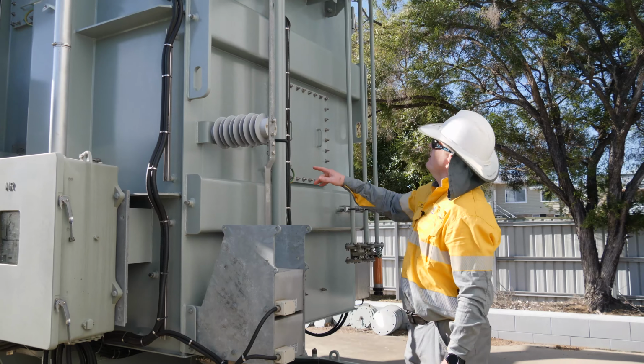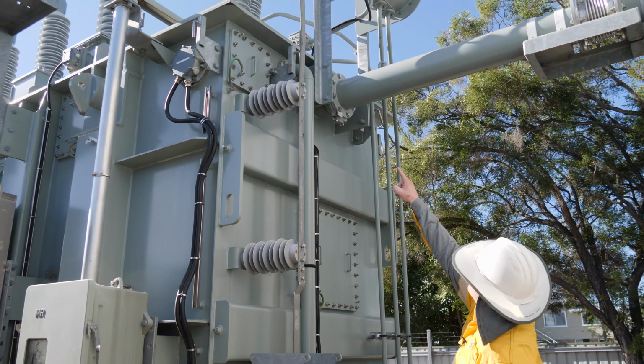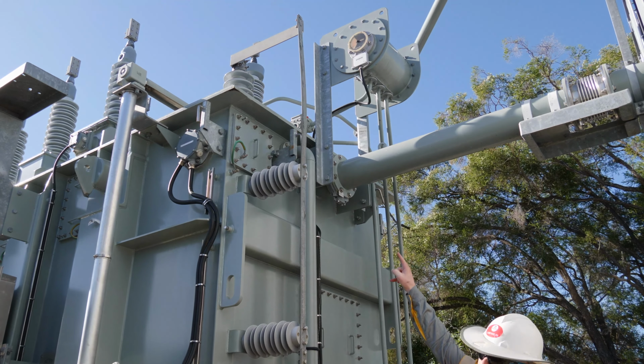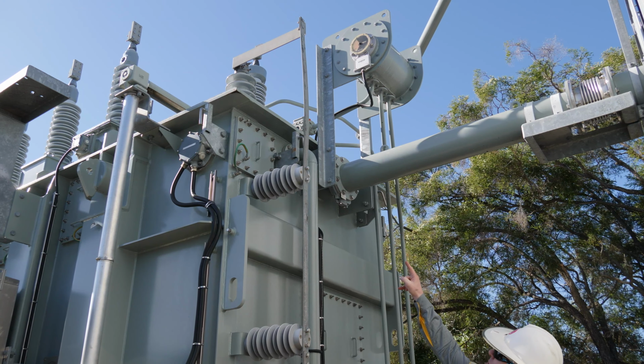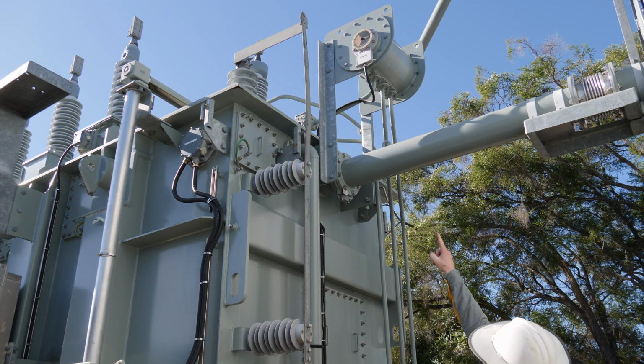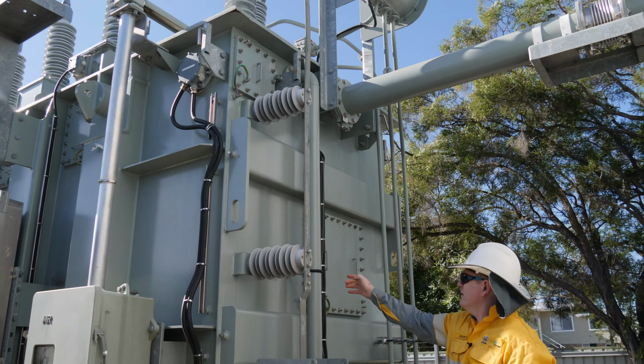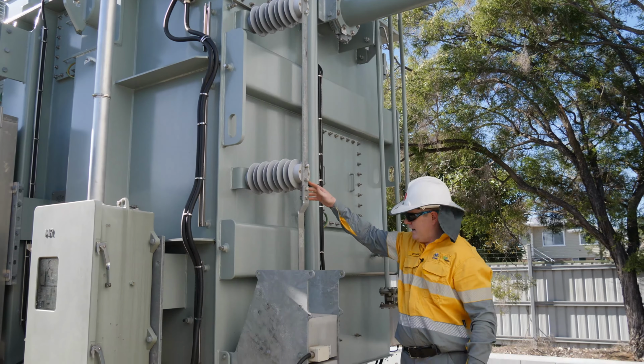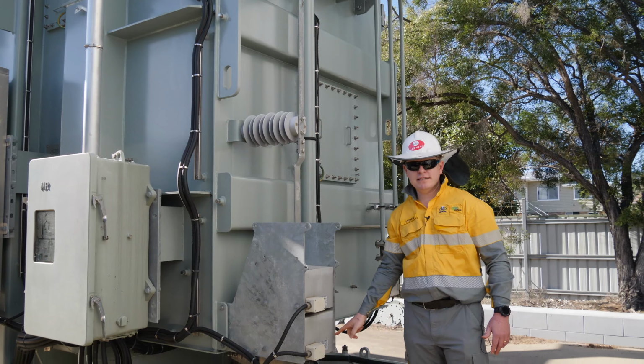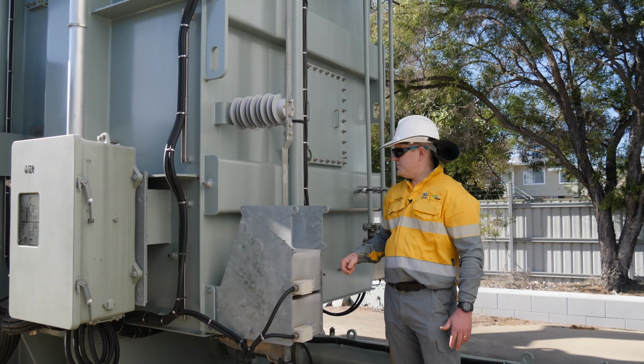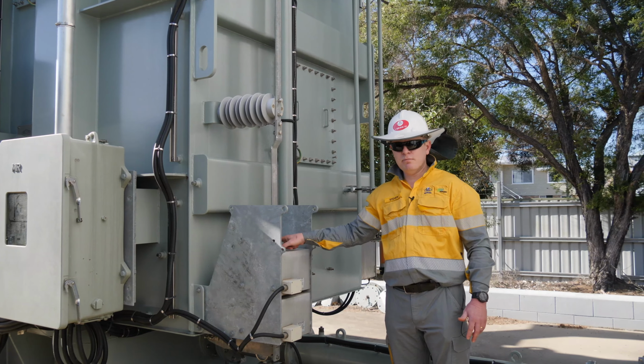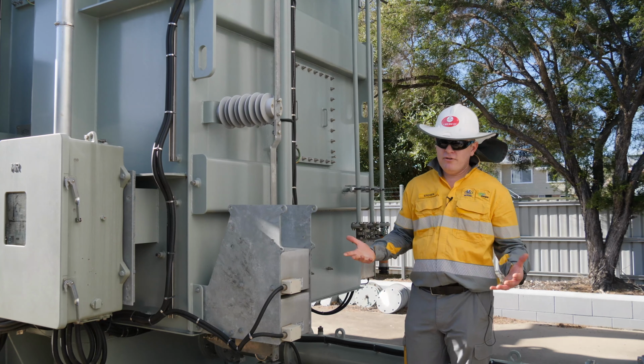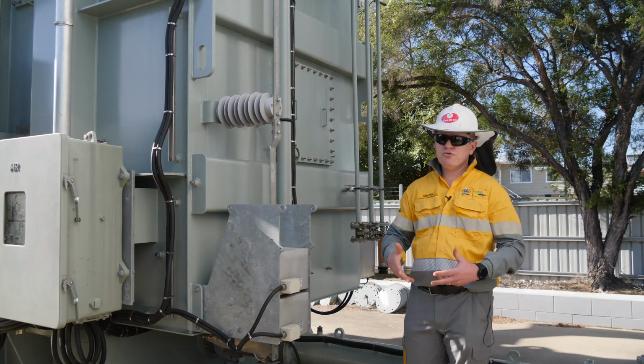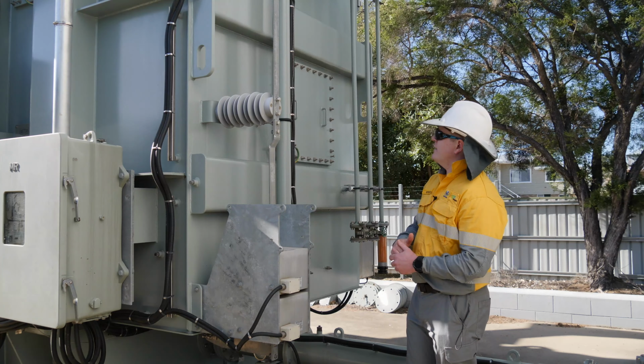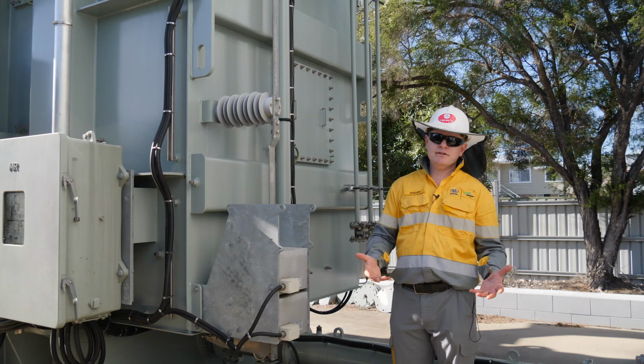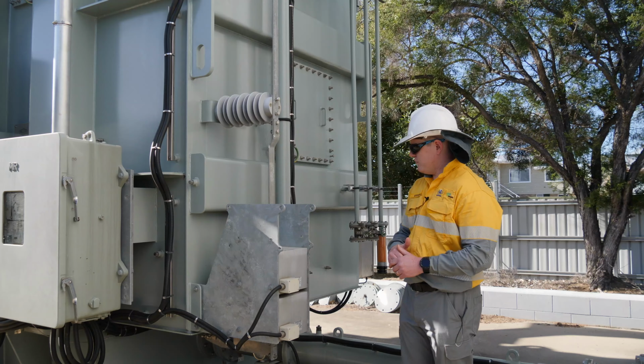So you can see there is a steel bar that comes off the neutral insulator on top of the tank, and this conductive bar comes down the side of the transformer. We have a couple of offset insulators, and it runs through 2 toroidal CTs. These CTs are used to measure any current flowing through this bar, and if there is a current flow, it means that we are getting a neutral return current, which means that there is clearly a fault somewhere on the system and we want to trip the transformer.